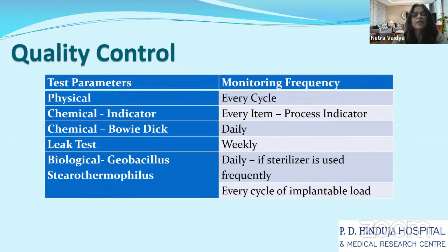Then you have a chemical indicator, which is put on every item, which we call a process indicator. It is easy for an end user to understand whether the item is processed through sterilization or not, and even if it is processed, whether it has passed or not. However, that's not something on which you can conclude that the item is sterile or unsterile. But these are the indicators which are used at user level.